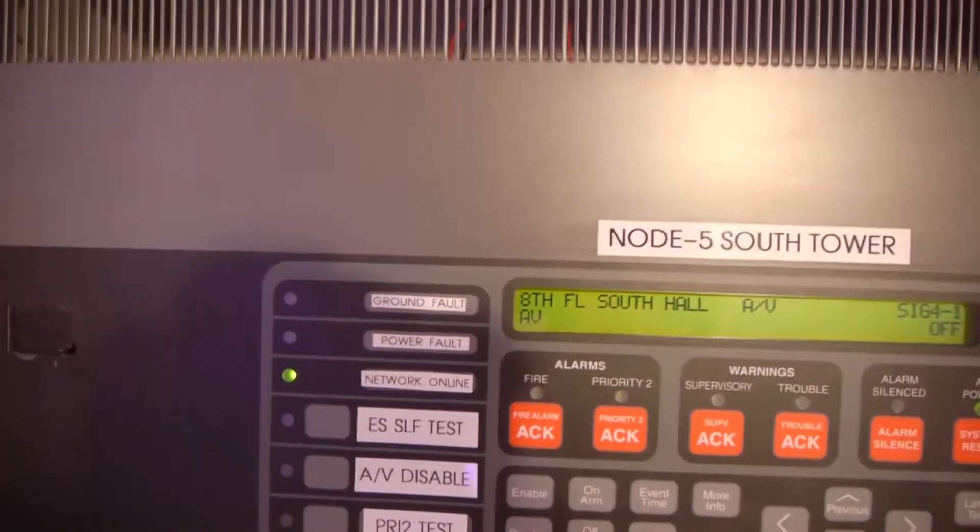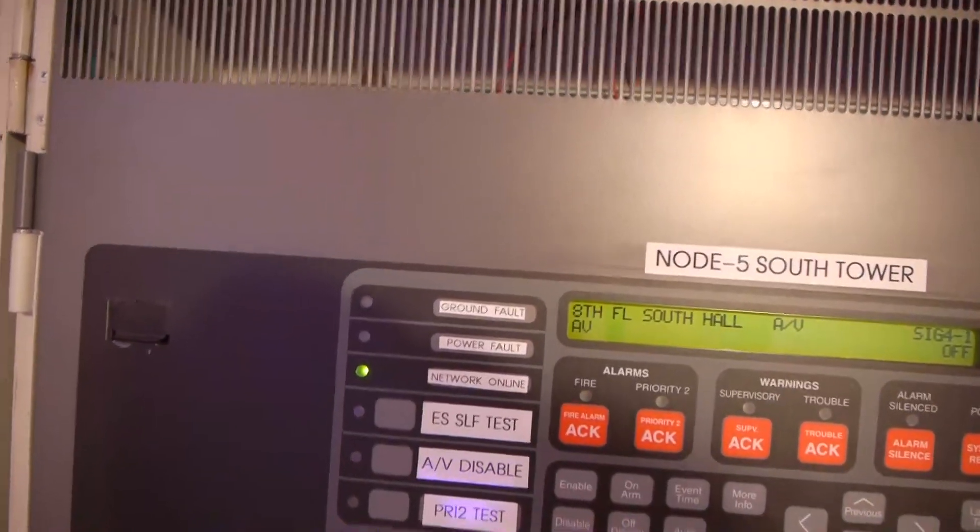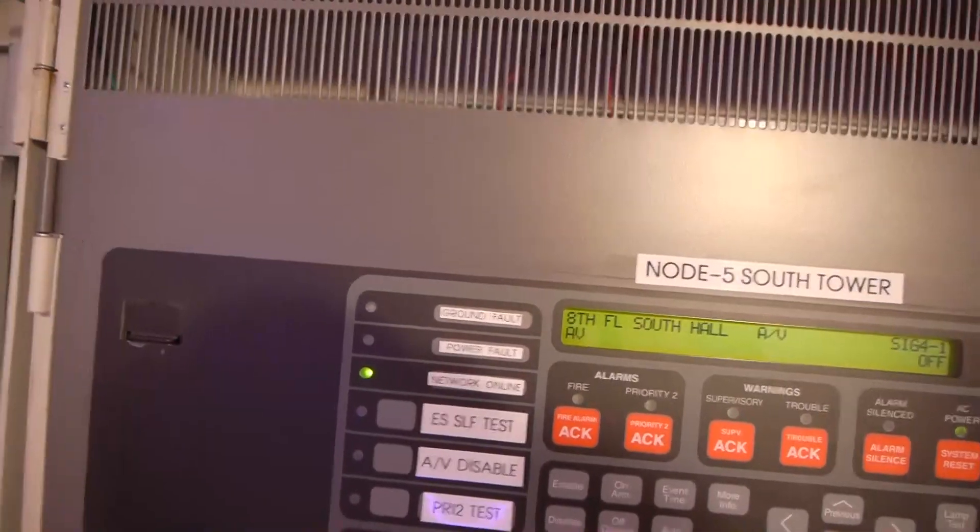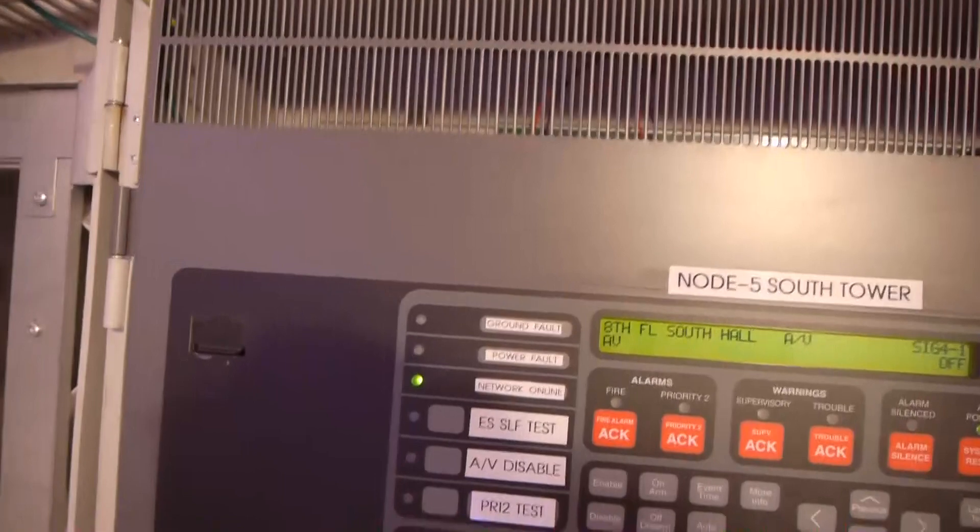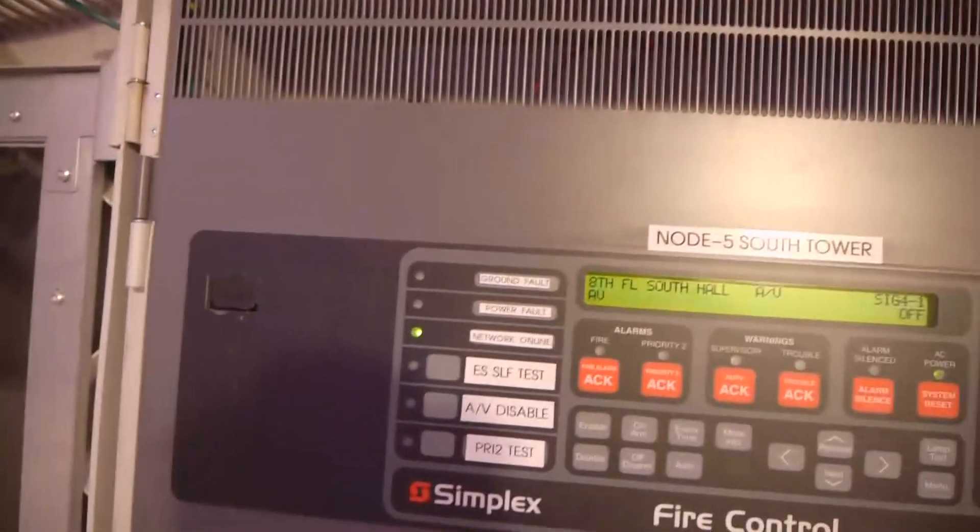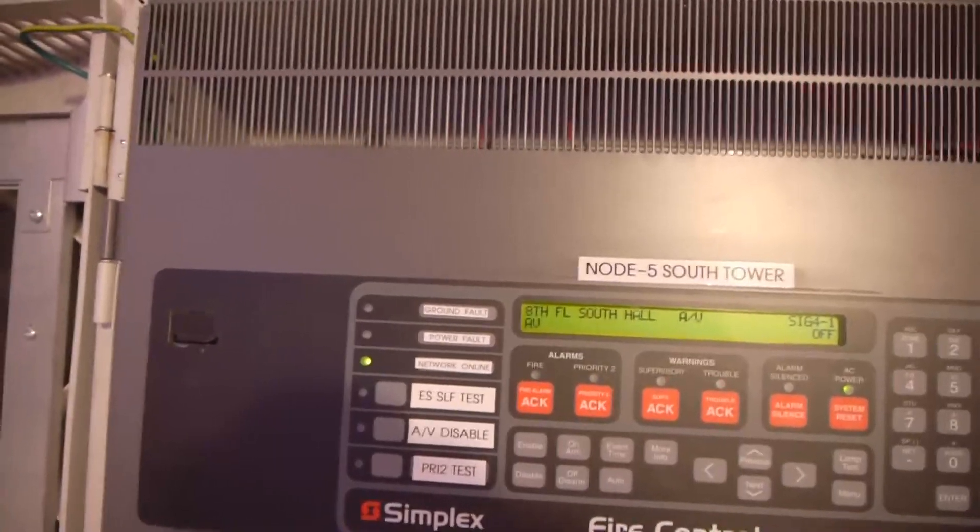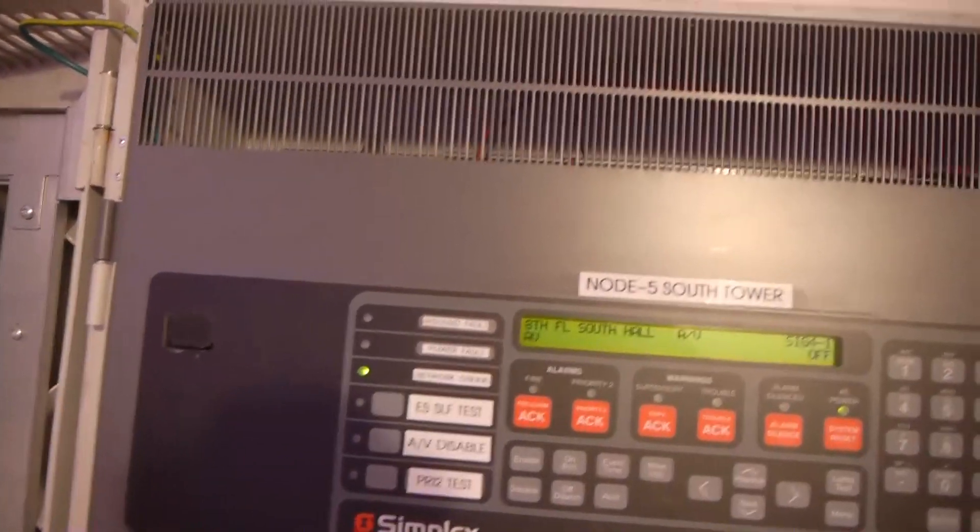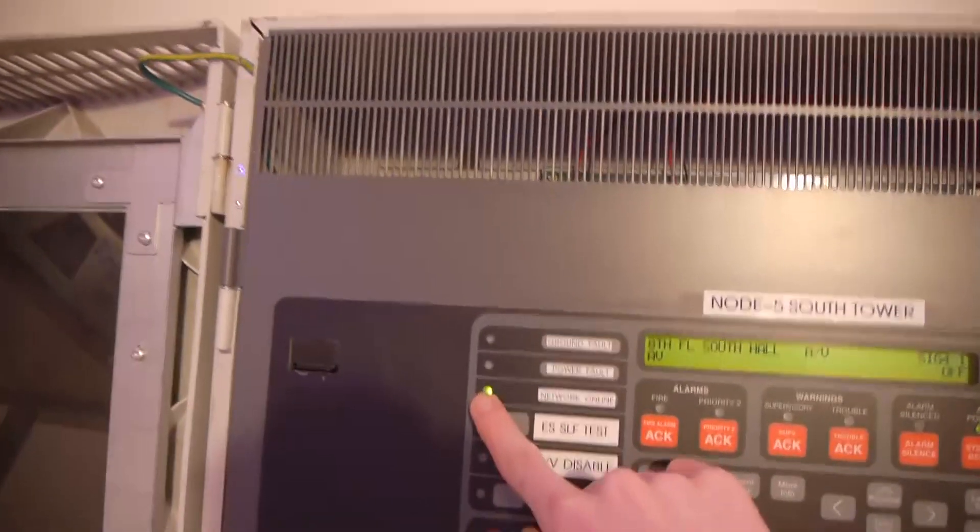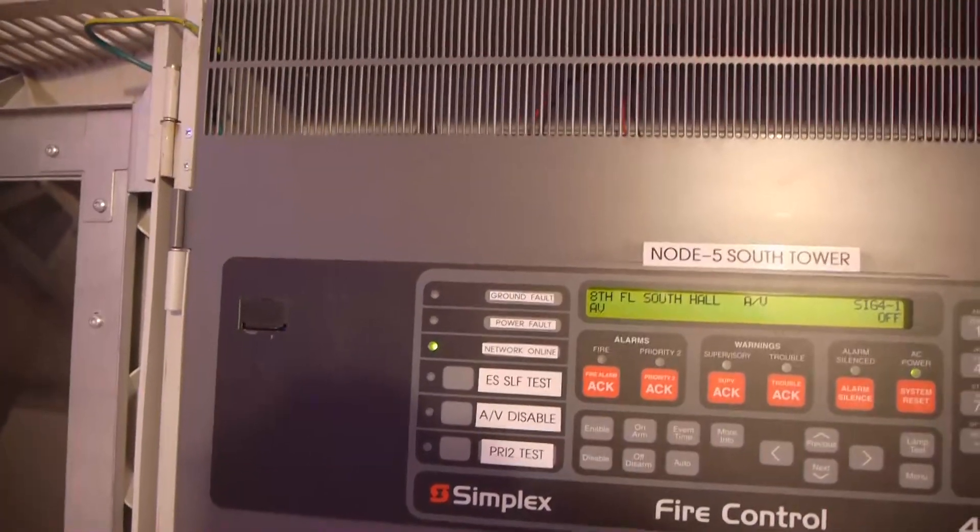Now above that we have three LEDs. One is the ground fault, power fault, which comes on if there's no AC or the batteries are missing, or if one of the IDnet channels is shorted or over current. And the network online, this is not connected to the rest of my 4100ES and 4100U network yet. That's where this says node 5s, because I'm planning on this being connected to it, but I'm still waiting for a network card. So right now this LED would normally only be on if it was connected to the network, but I just programmed it to be on 24-7 because it's kind of nice to have the green light.